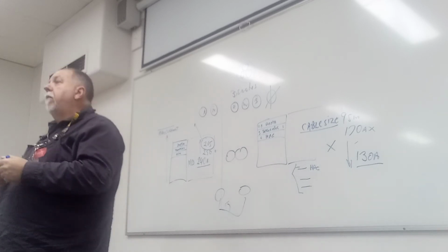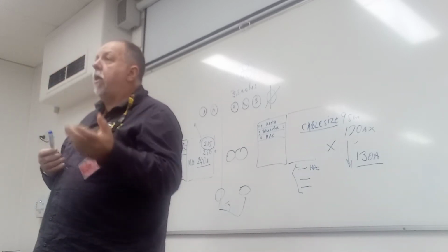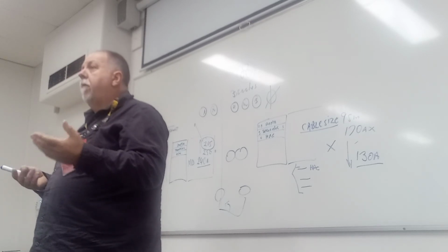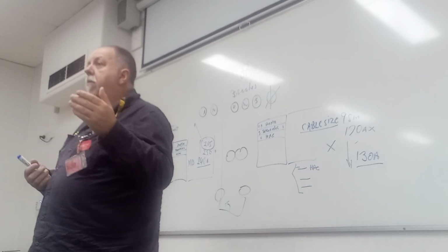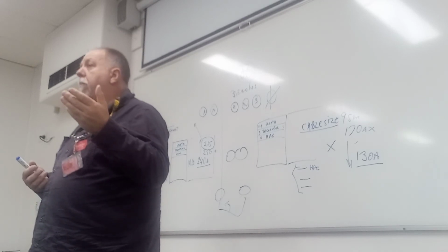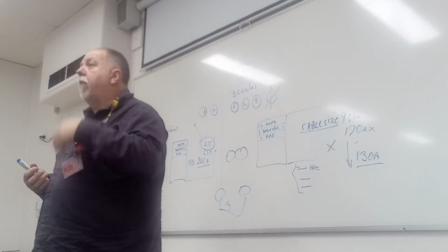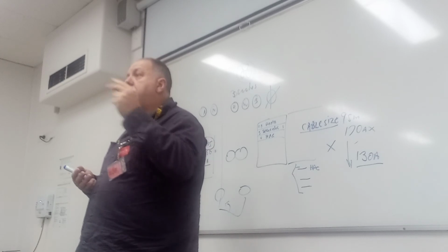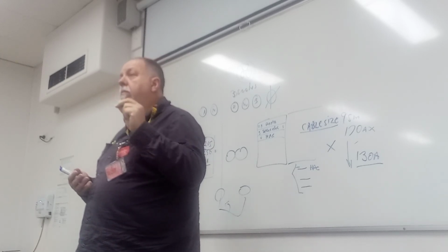All right. The first thing I always say, you also got to look at the question too. Two types of questions work backwards. If you've got one with maximum demand, and it says that the hotel's got, for example, 400 amps, and it's going to drag 2 cables in parallel. What will be the size cable I need? What's the first thing that people don't do? Don't divide.